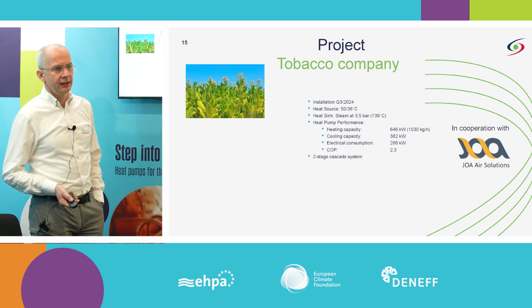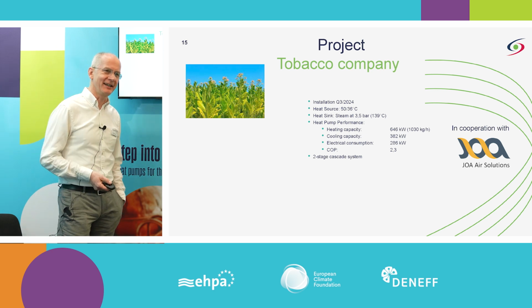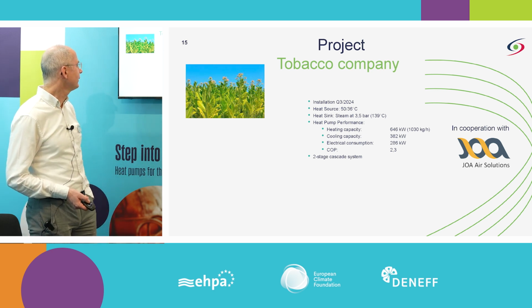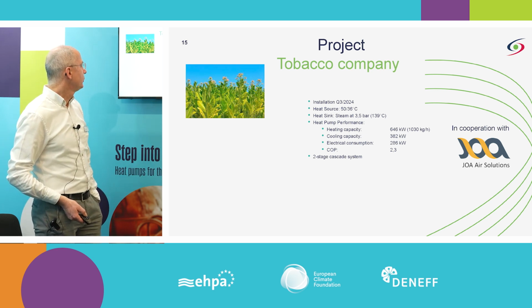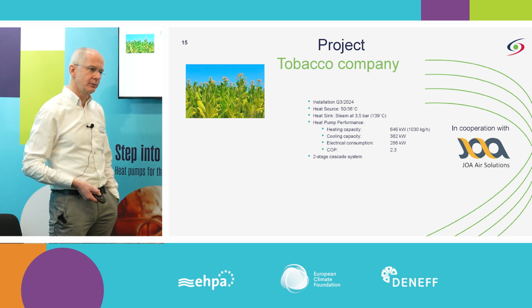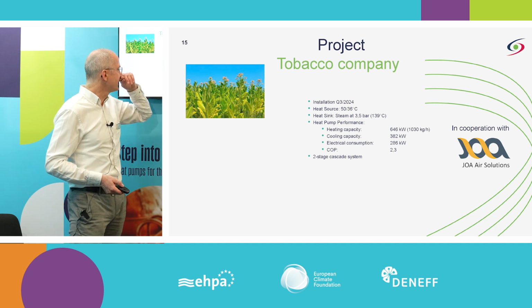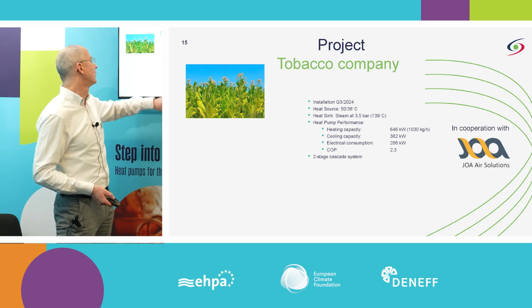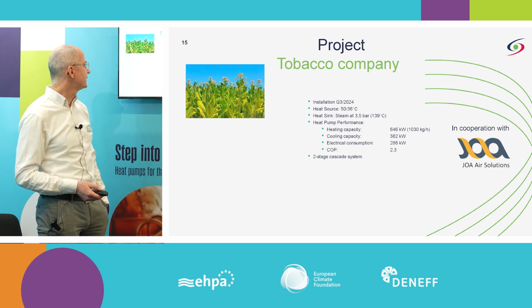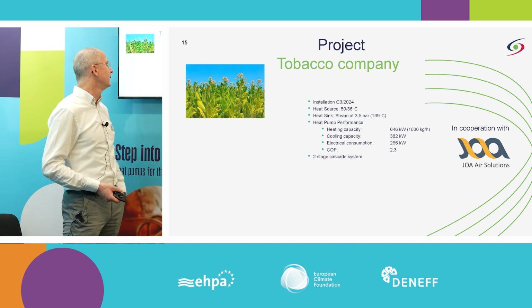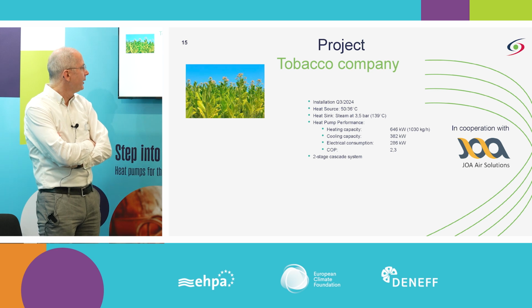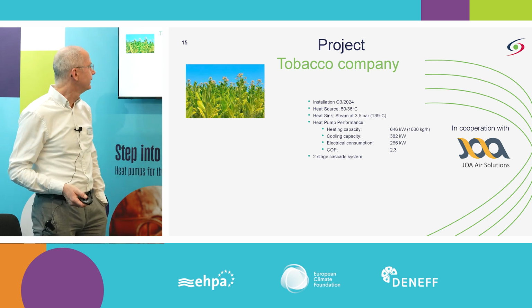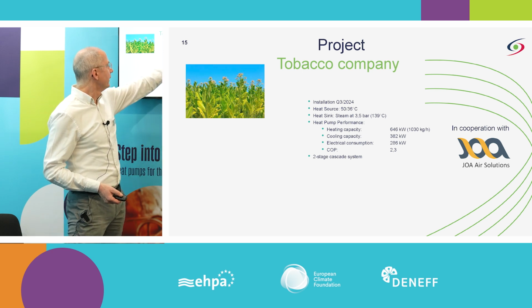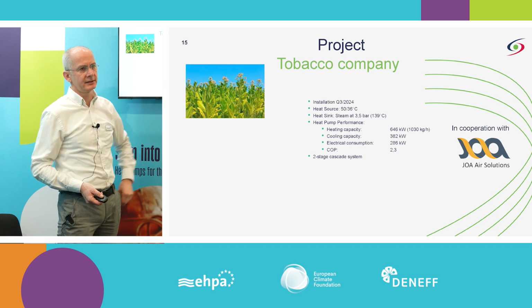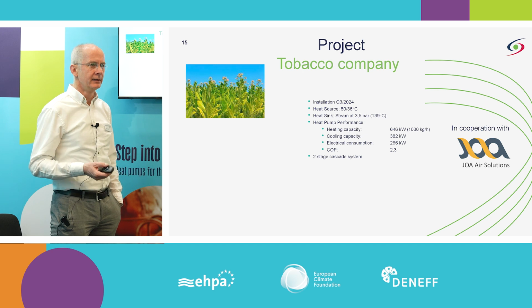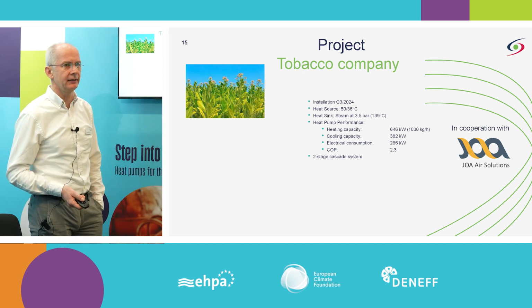Now a project which will be installed in summer. It's not really food, it's tobacco. We will install a unit, currently under production, to be installed in summertime with a heating capacity of 600 kilowatts. It's a relatively high temperature lift: we get in with 50 degrees and need to cool it to 36 degrees. The temperature we produce is around 140, or 139 degrees, as steam. We always calculate from this lower point to the steam temperature, so it's a temperature lift of 100 degrees, and for this COP of 2.3, I think it's still acceptable.